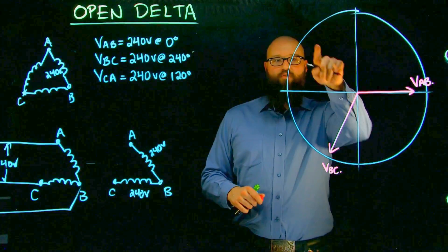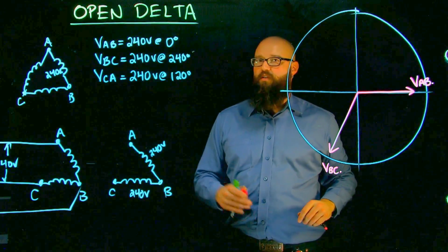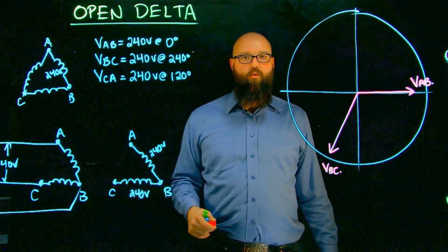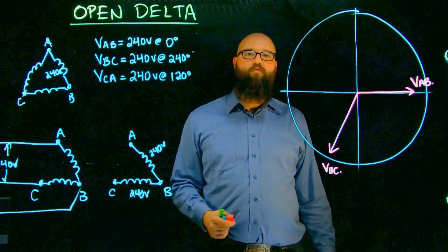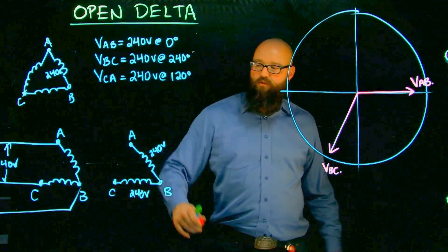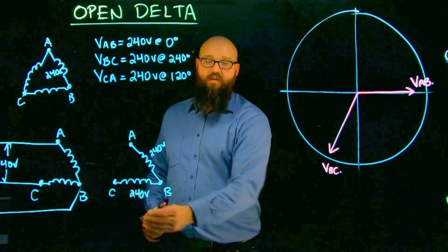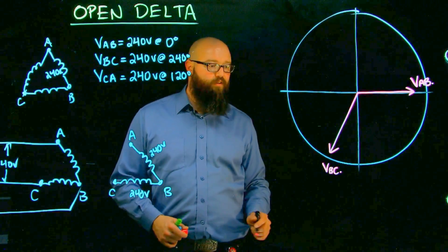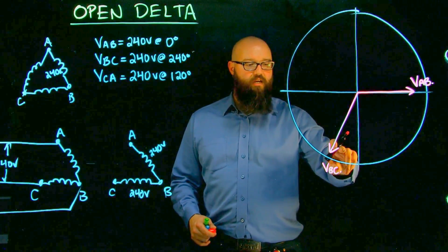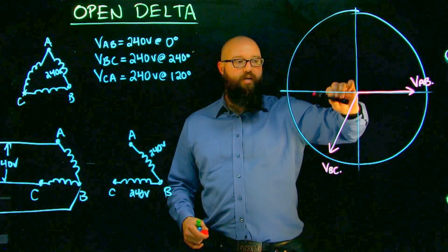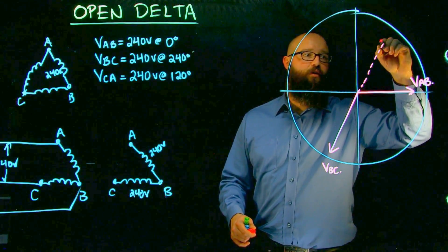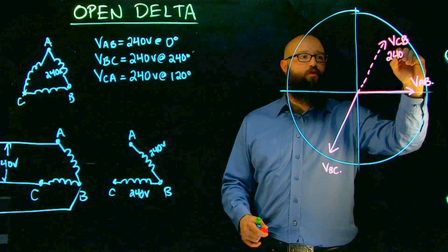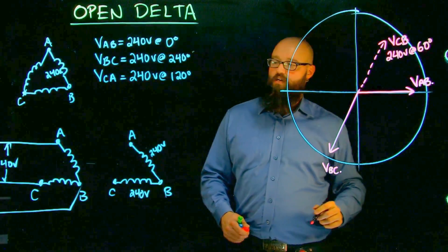V C to A, though, this one is gone. Now, is it truly gone? Let's find out. If I wanted to measure C to A, I don't have a coil there anymore, but what I can do is backtrack through my transformer to prove that that voltage is still there. If I go from C to B, that is the opposite of B to C. When I say the opposite, we're talking about 180 degrees difference. If V B to C is at 240 degrees, well, 180 degrees from that, we have V C to B, which is 240 volts at now 60 degrees.